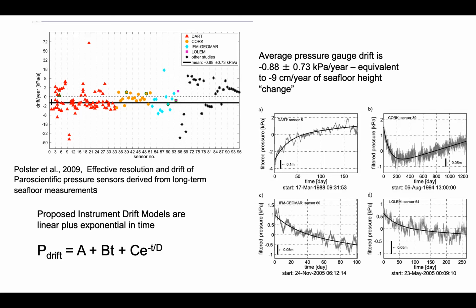You can't pre-stress a gauge and expect it to maintain that afterwards. You can't just put one on the rack and age it like a nice ham and expect it to have low drift. And if you deploy them, bring them back, and they sit on the shelf for a year or whatever, this exponential term, which we hope is of variable length, could restart, and it can behave in an entirely different way. So your basic laboratory calibration doesn't have a whole lot of impact on understanding what the gauge is going to do going forward at a new point.